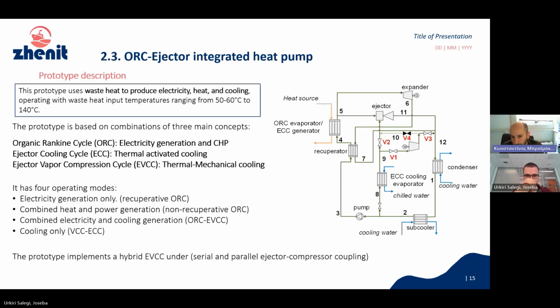Again, we have the ORC. But what happens in this case is that we don't use the recuperator because we prefer to utilize the heat of the expanded vapor to produce useful thermal energy. And then we have another operating mode that is combined electricity and cooling generation. So this is CCP mode. And what happens in this case is that we have the operation of the ORC, and at the same time, we also operate the ejector vapor compression cooling cycle.